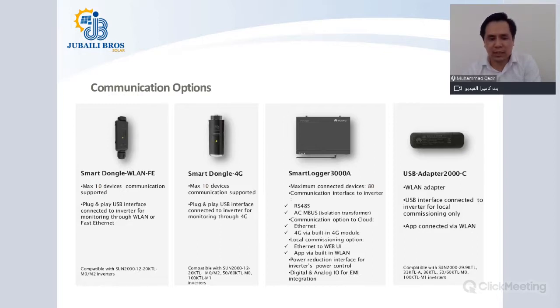Smart Logger 3000A, it can connect up to 80 inverters. Communication to Smart Logger 3000A happens via Modbus TCP with to the router, and with the inverter it speaks over RS485. It supports AC bus, Ethernet, 4G, and the user interface for the Smart Logger is Web UI, and it has a built-in Wi-Fi as well.